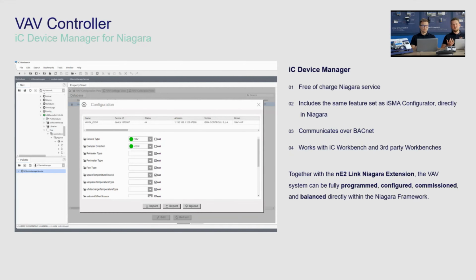But to make it much easier than just going through all the BACnet objects, we developed a special service that gives you the same feature set as you see in our iSMA configurator, but directly in the Niagara Workbench itself. So once you take the service, put it in your station's services, and you have your BACnet devices already available in the BACnet network, you'll be able to seamlessly access the configuration of the VAV units. And even if you have them pre-configured already, either using the wall panel or from the iSMA configurator, if anything changes, you can always access this application directly through the software.